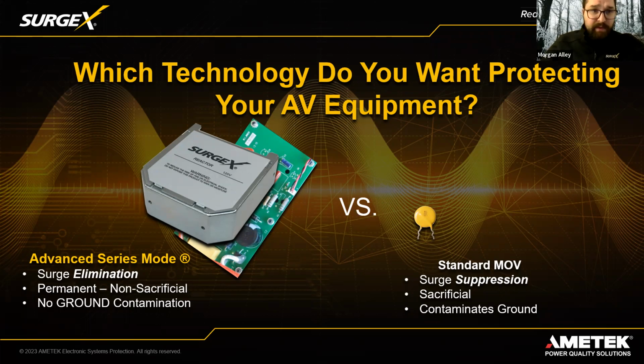On the right, you see this little yellow circle, called an MOV, or metal oxide varistor. That's essentially what 99.9% of the market uses for surge protection. MOVs are literally just a little piece of metal wrapped in a coil designed to disperse some energy, and over time, they're designed to fail. Being a self-sacrificial product diverting energy, you're not looking at longevity, and you are contaminating ground, which causes a lot of those lockups.